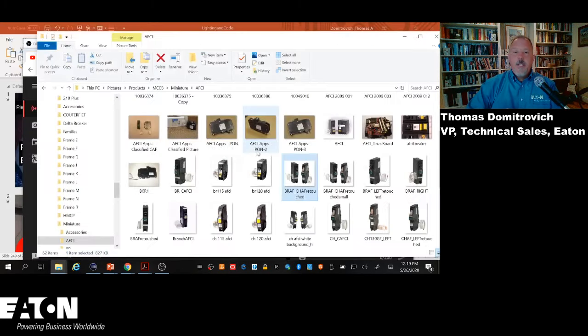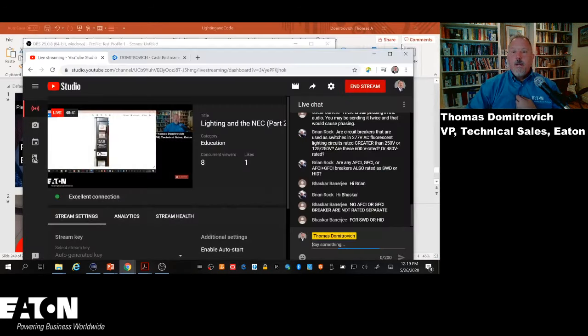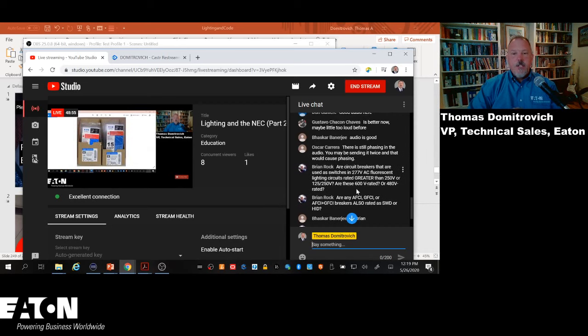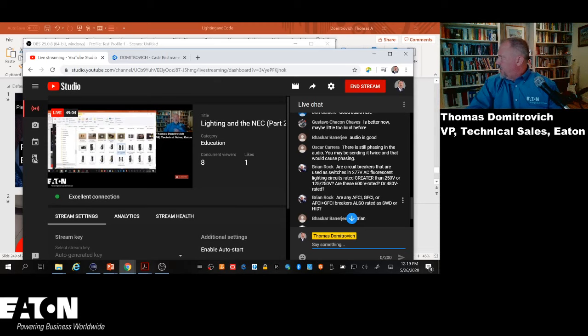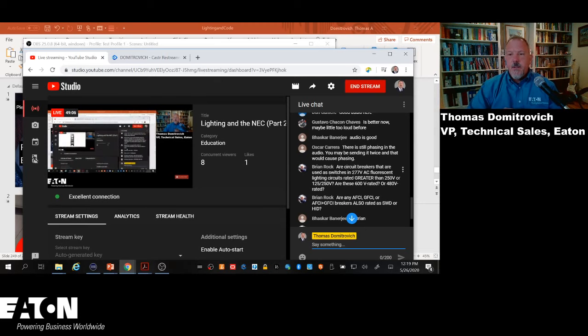That's just how it's packaged. All right, so I don't have SWD to answer your question, Brian. No SWD, doesn't look like SWD nor HID. Not rated separate. Okay, we got our AFCIs, GFCIs also rated as SWD, HID. So based on the images that I have, I would have to say no, that would not be the case. I don't know. I might have an AFCI over here as well.